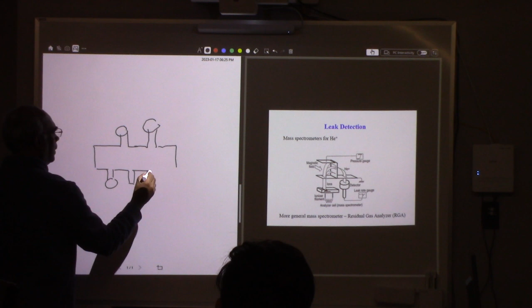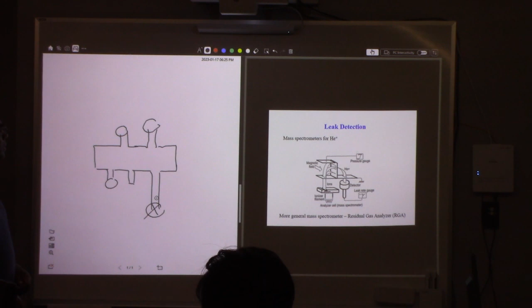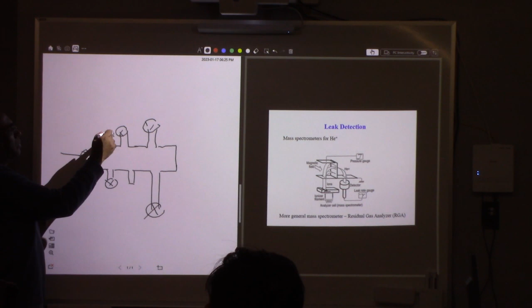If you have a big leak, that's very easy. What we typically do is, suppose this has many connections and I just draw something like this. You have some connections. One way to do it is first close everything, then you can pressurize this with, suppose I have a tube here, maybe helium gas or nitrogen gas. You pump it and just put some soap solution around all these connections. If it's a big leak, you will see some bubbles coming out, right? Then you can see there's a leak. But you can only do that for a real big leak.